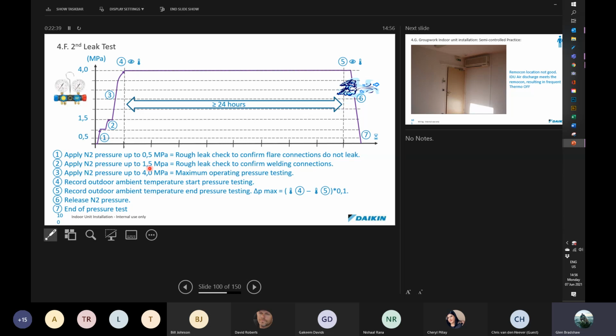Then you can take it to 1.5 megapascals. Also a rough check confirming welding connections, and then anywhere between 35 and 40 bar. Do not advise that you go above 40 bar. Do make sure that your gauge is calibrated correctly, and your regulator as well, so that you're not going to overpressure and burst any pipes, or damage indoor units.